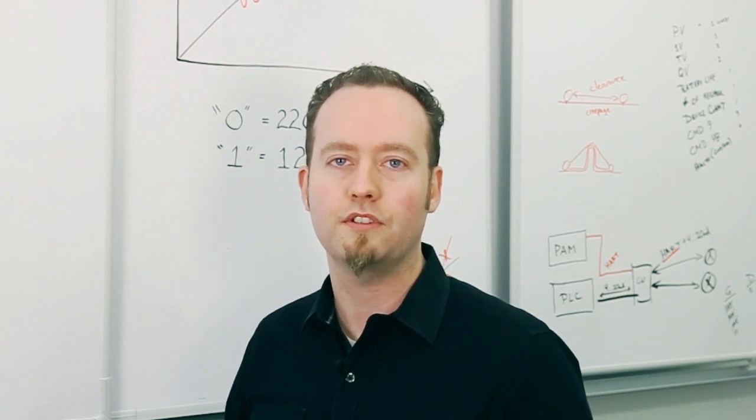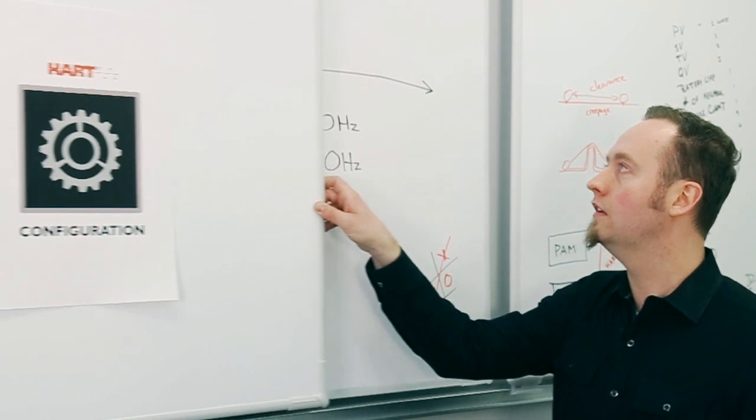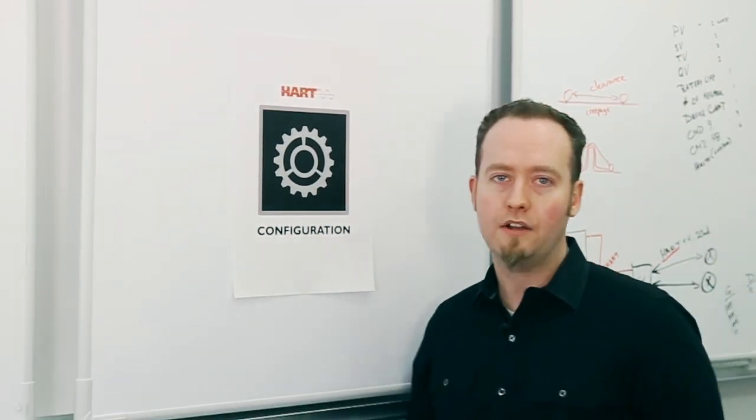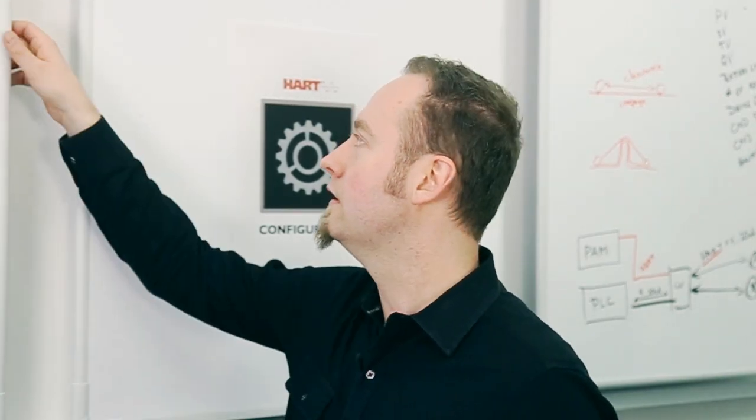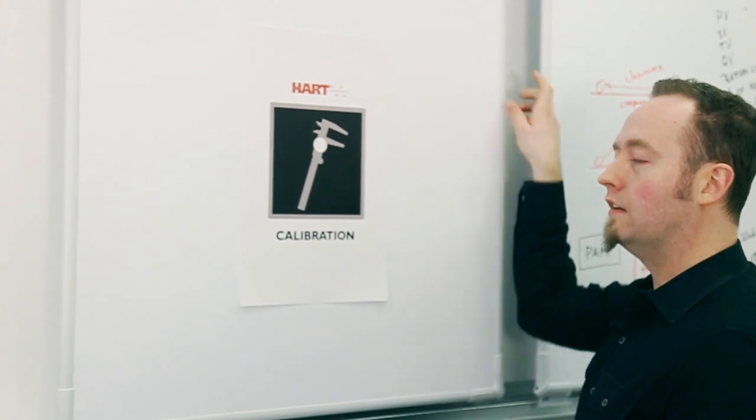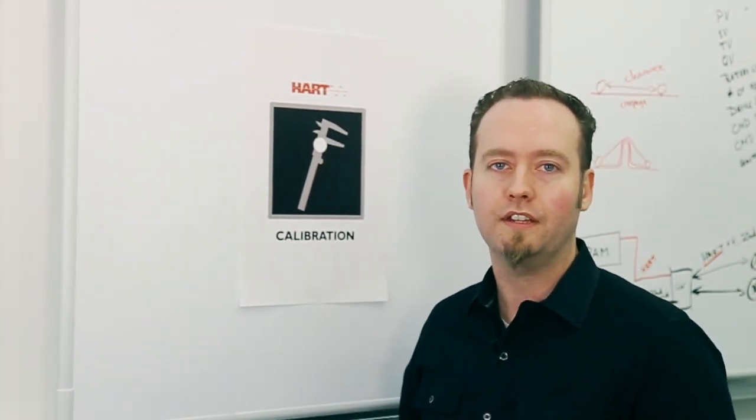The most basic use of HART allows you to configure your devices. Name your device with a device tag for easy identification. The measurement range, engineering units, and sensor type can also be selected. After the initial installation and configuration, the device can be calibrated to set the zero and span, trim the 4 to 20 milliamp signal, or account for other external sources of measurement error.